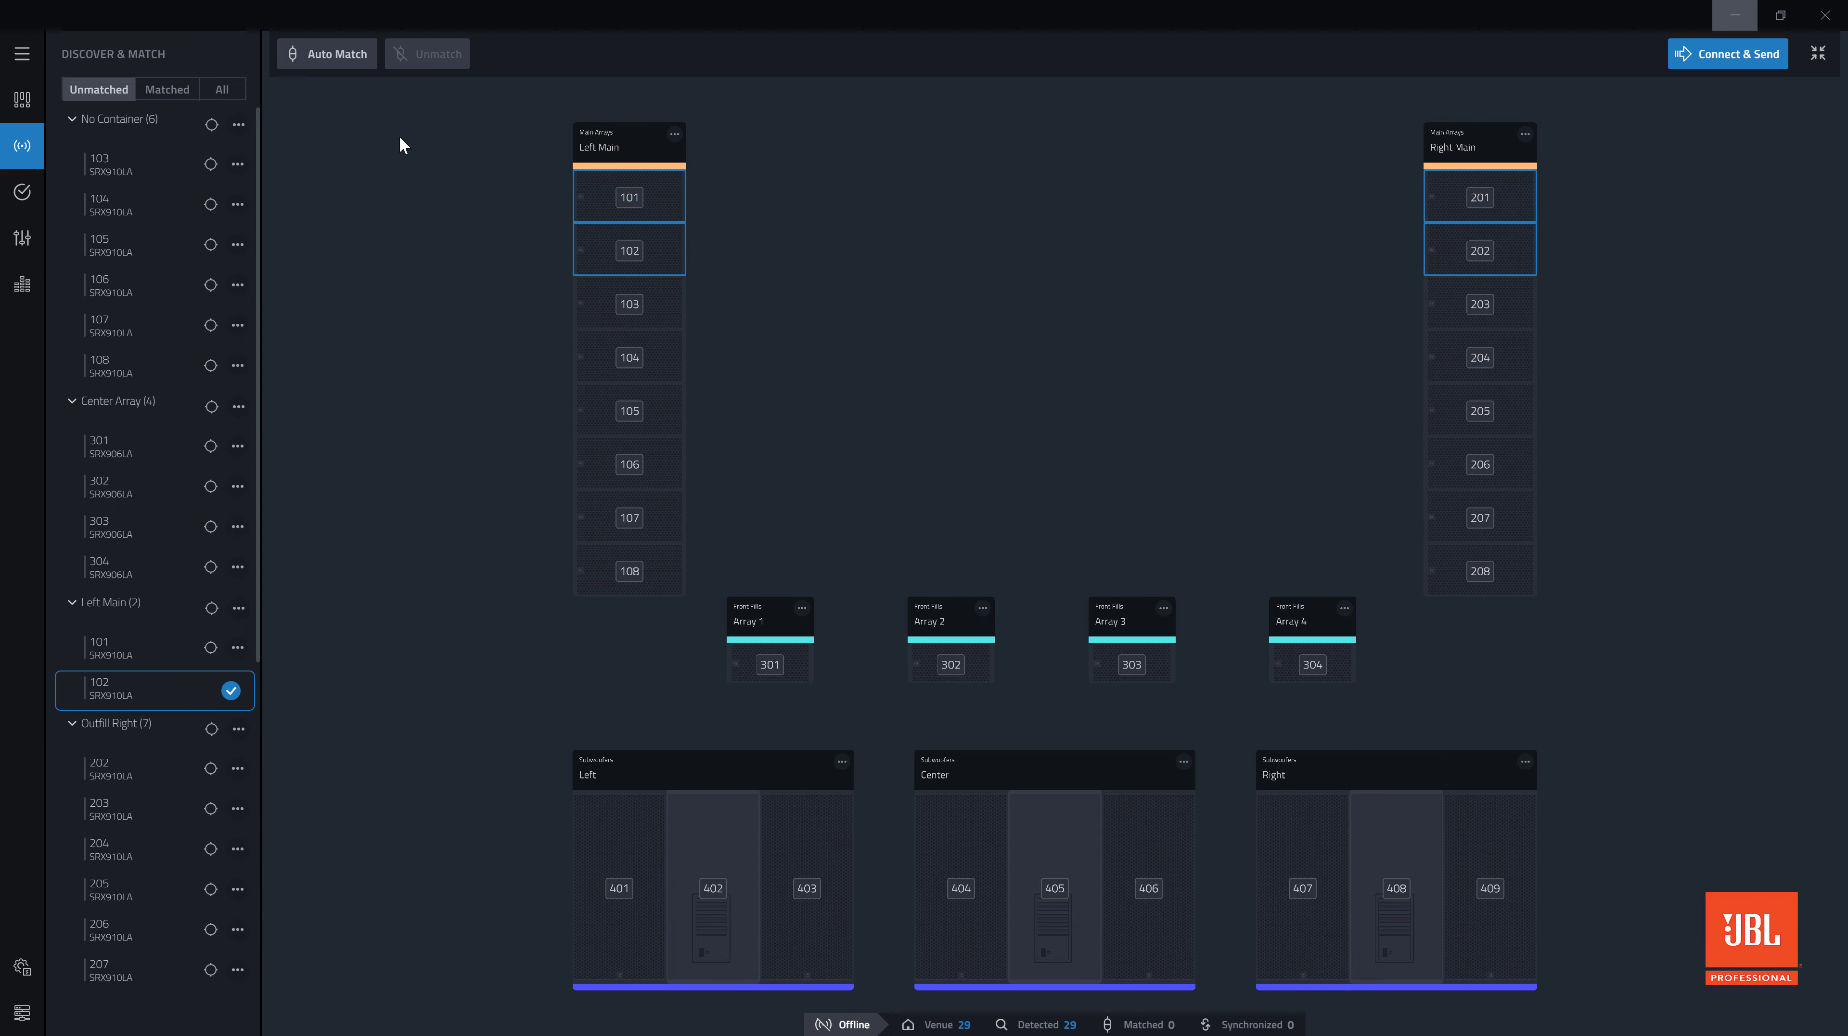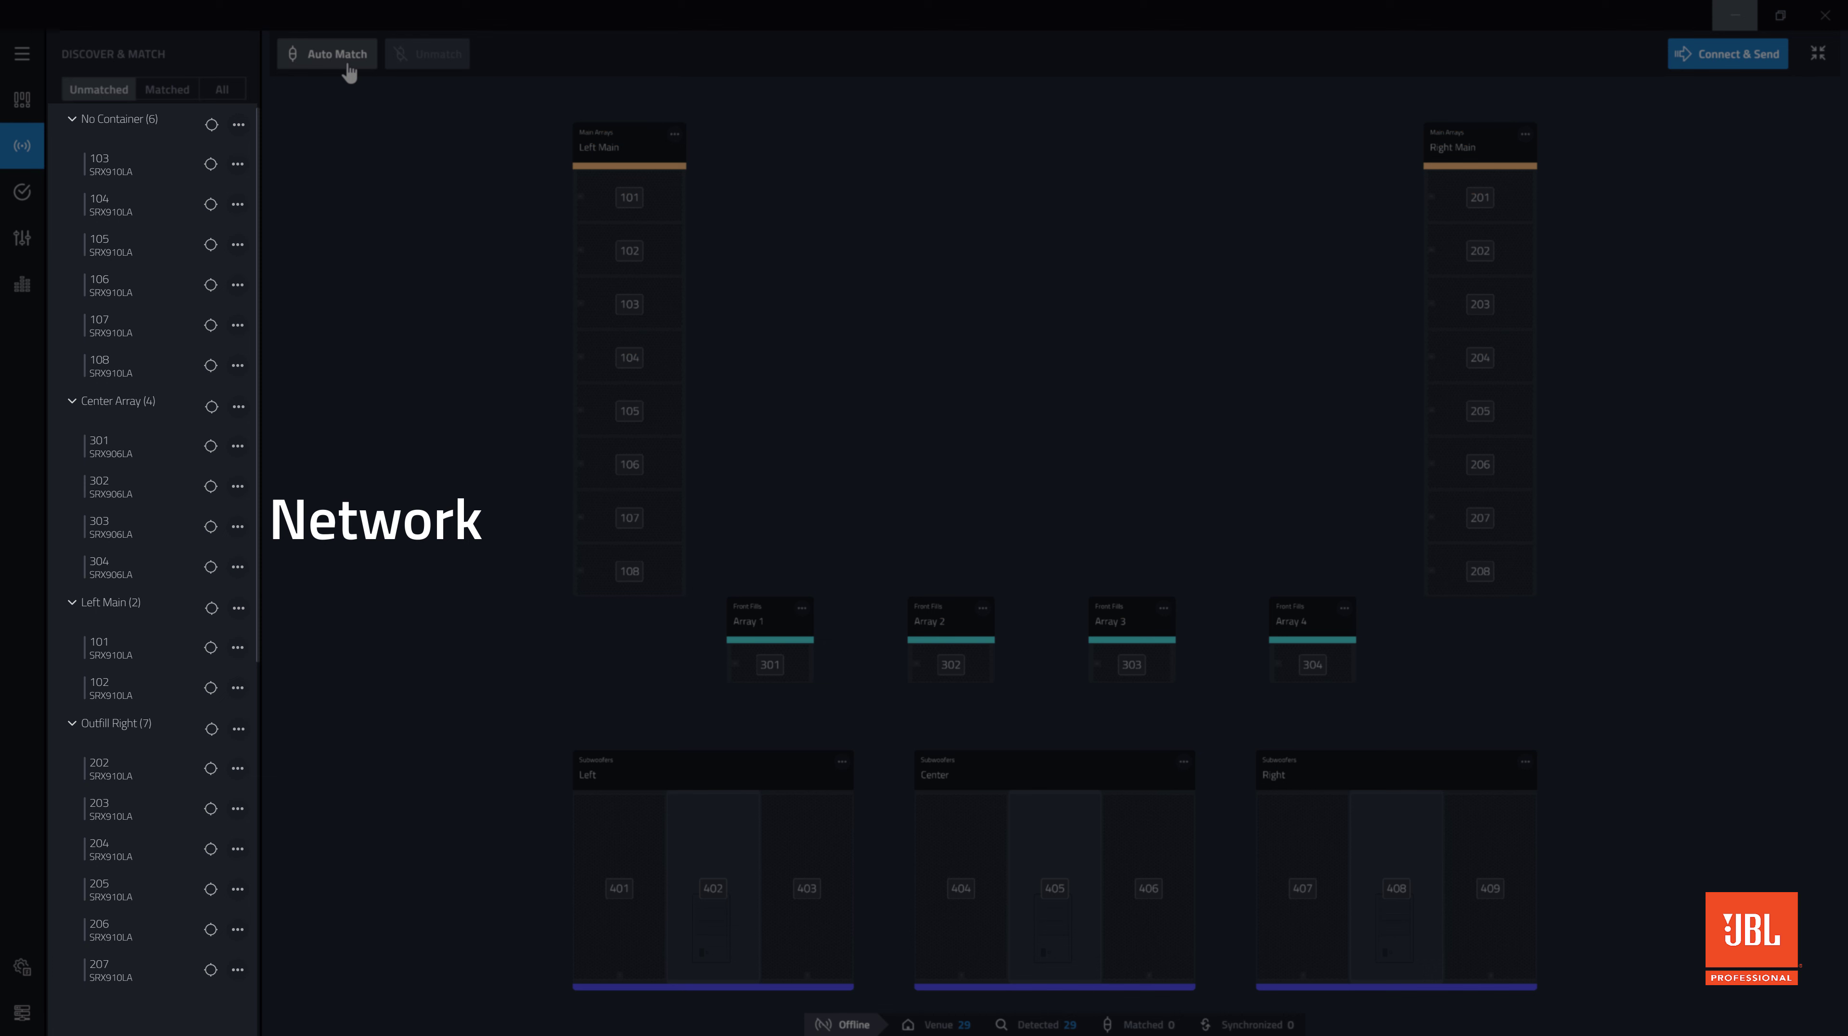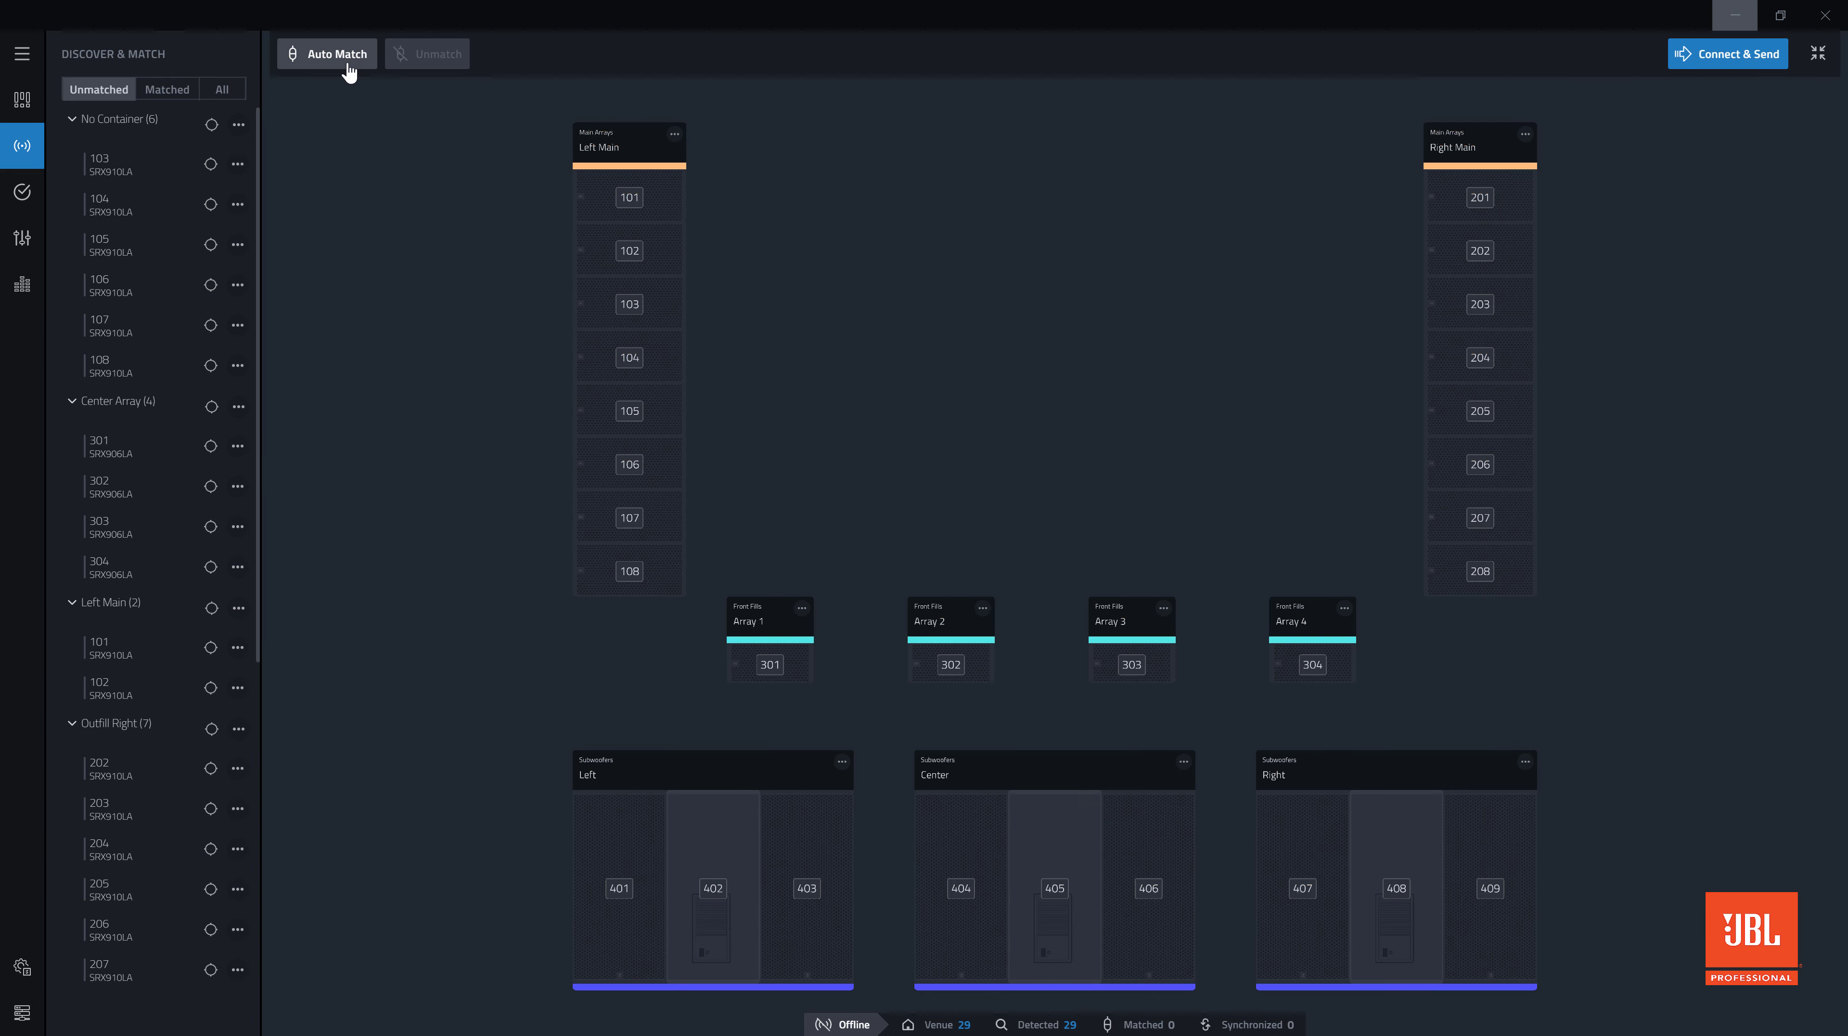The quicker and preferred method of matching an entire network of devices is to use the automatch function. For automatch to work correctly, the HCIDs and device types in your design file must match the HCIDs and device types of the devices on your network. If they do not, NetSetter can be used to change the online device HCIDs.